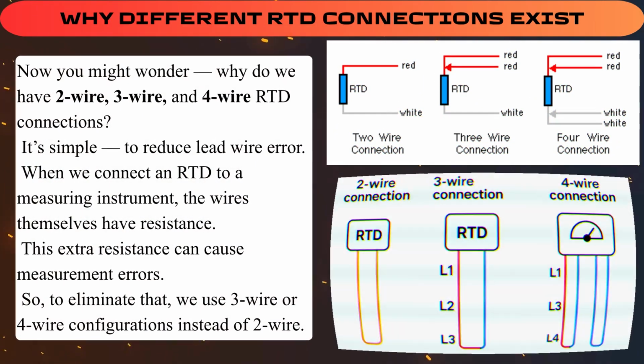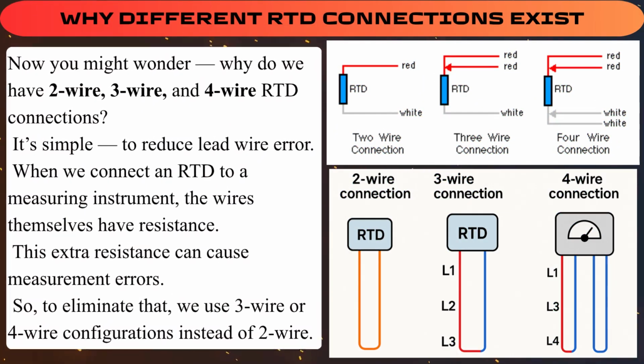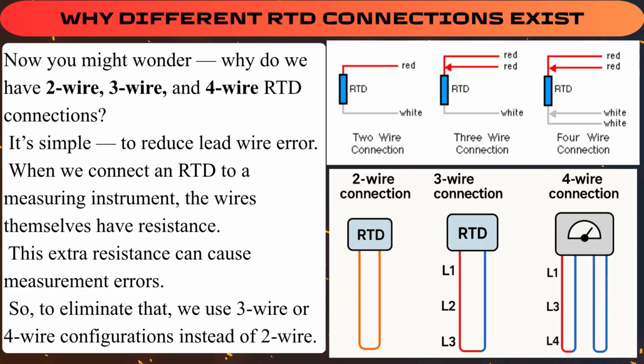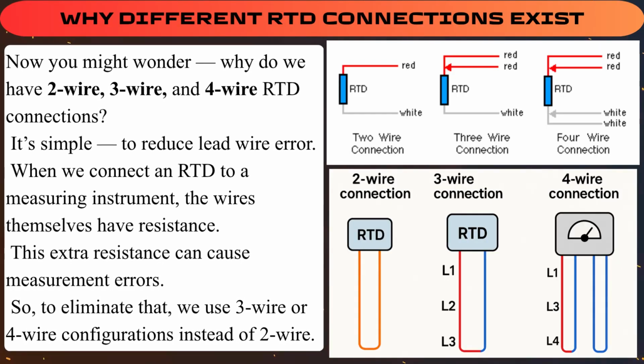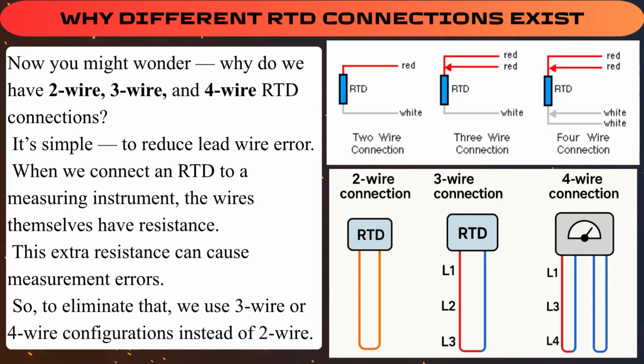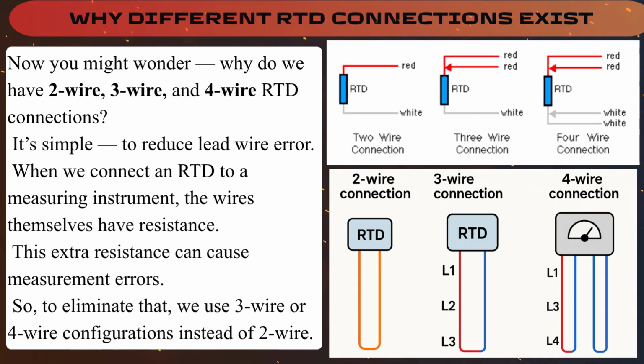Why different RTD connections exist? Now you might wonder, why do we have 2-wire, 3-wire, and 4-wire RTD connections? It's simple: to reduce lead wire error. When we connect an RTD to a measuring instrument, the wires themselves have resistance. This extra resistance can cause measurement errors. So, to eliminate that, we use 3-wire or 4-wire configurations instead of 2-wire.